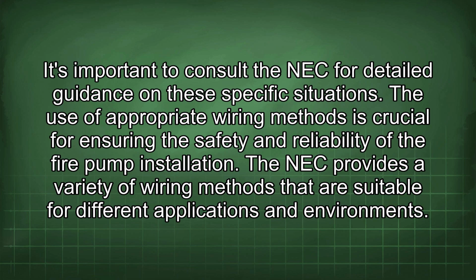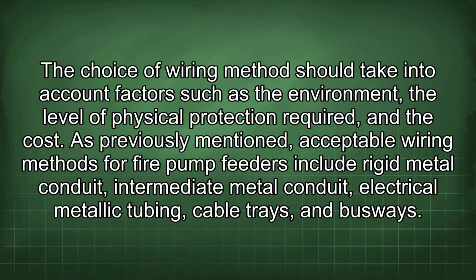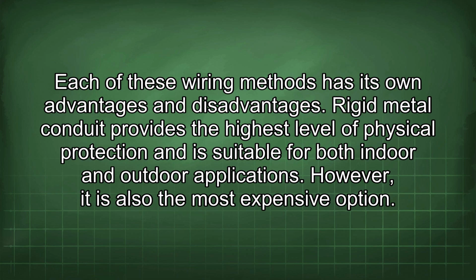The use of appropriate wiring methods is crucial for ensuring the safety and reliability of the fire pump installation. The NEC provides a variety of wiring methods that are suitable for different applications and environments. The choice of wiring method should take into account factors such as the environment, the level of physical protection required, and the cost. As previously mentioned, acceptable wiring methods for fire pump feeders include rigid metal conduit, intermediate metal conduit, electrical metallic tubing, cable trays, and busways. Each of these wiring methods has its own advantages and disadvantages. Rigid metal conduit provides the highest level of physical protection and is suitable for both indoor and outdoor applications.